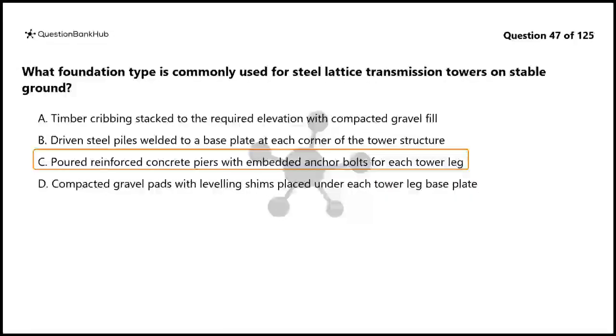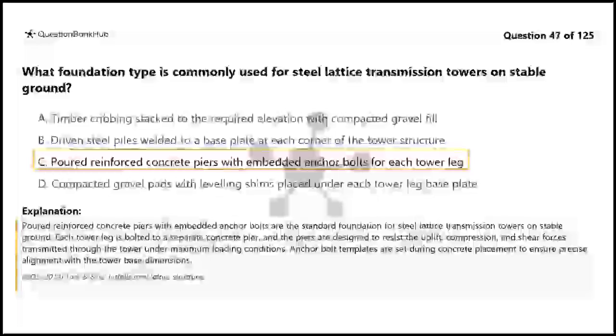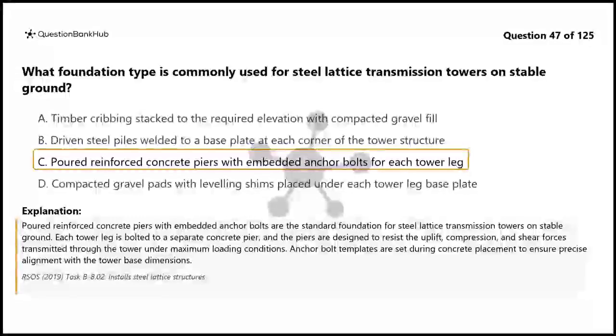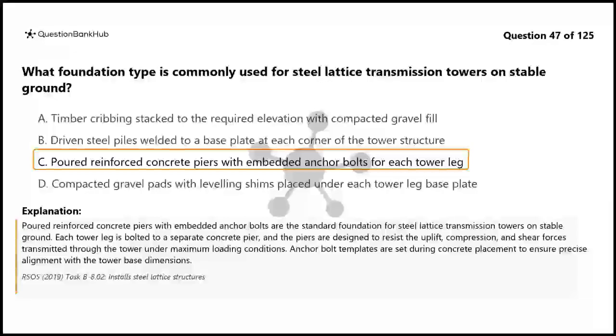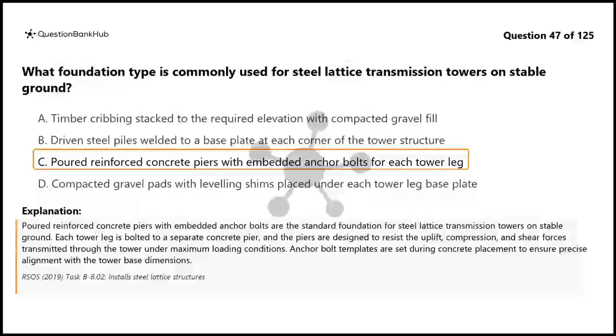The correct answer is C. Poured reinforced concrete piers with embedded anchor bolts are the standard foundation for steel lattice transmission towers on stable ground. Each tower leg is bolted to a separate concrete pier, and the piers are designed to resist the uplift, compression, and shear forces transmitted through the tower under maximum loading conditions. Anchor bolt templates are set during concrete placement to ensure precise alignment with the tower base dimensions.